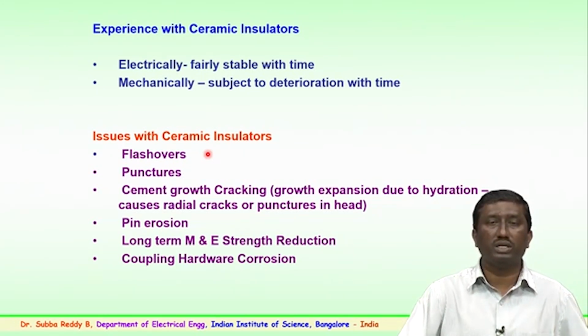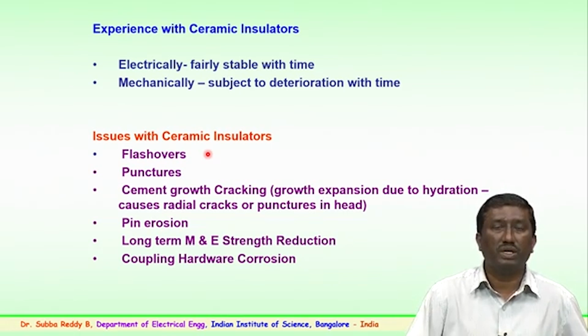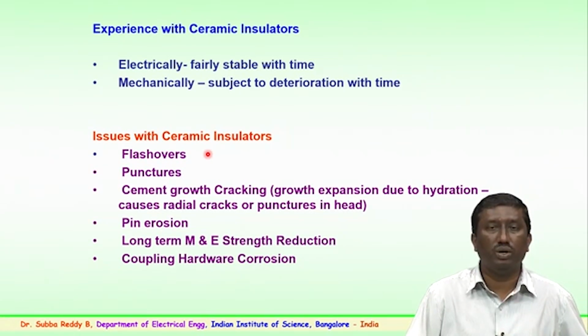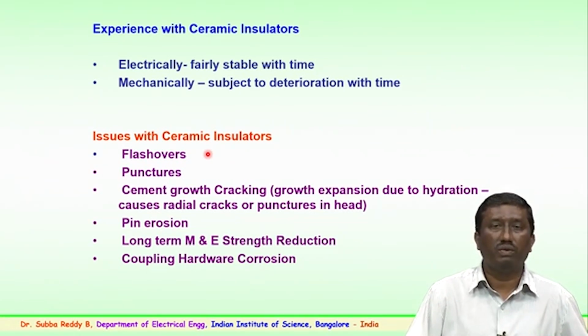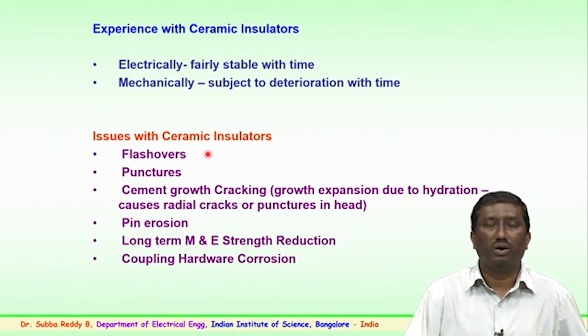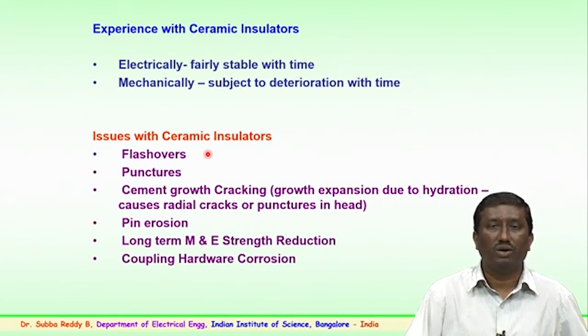The next issue is punctures. Puncture of insulators has also been noticed in the field, because of natural lightning, over voltages, or very sharp rise of surges, where punctures on the ceramic shell have happened and the insulation level has been reduced.